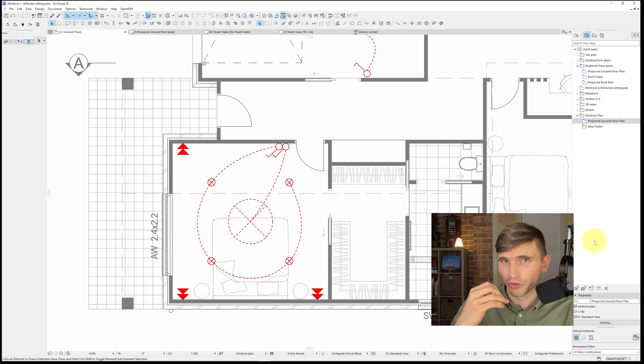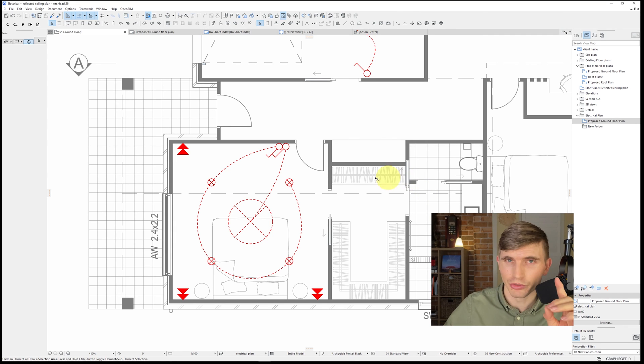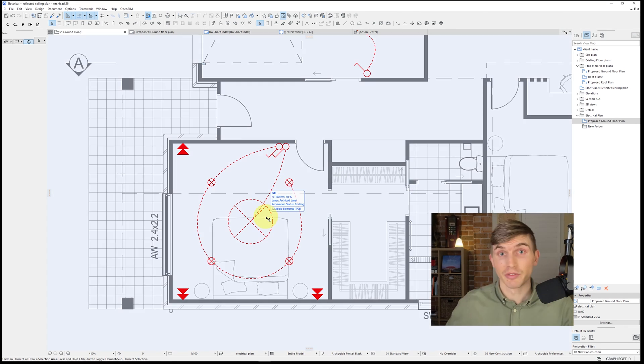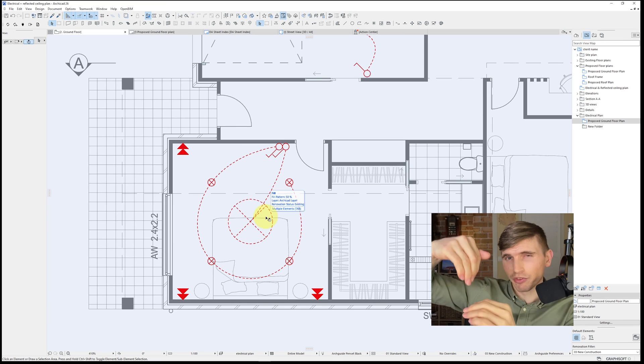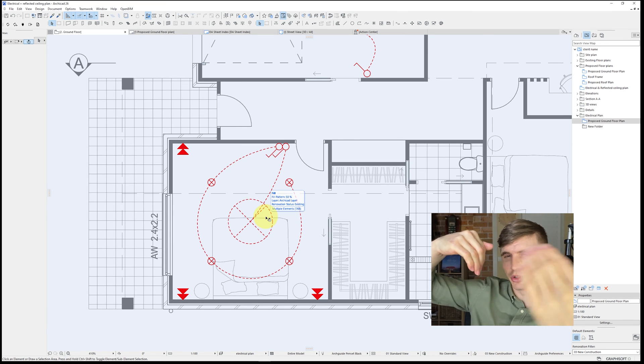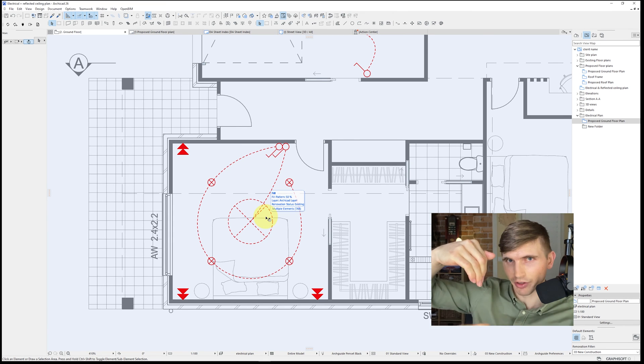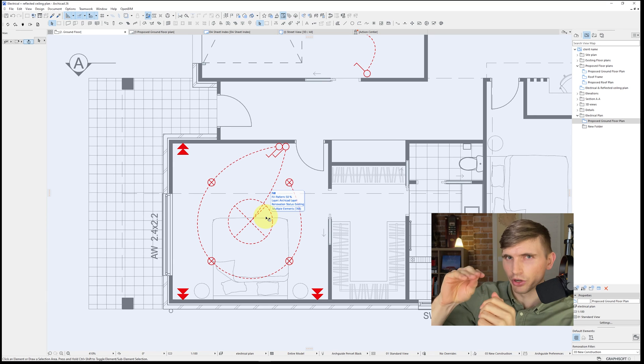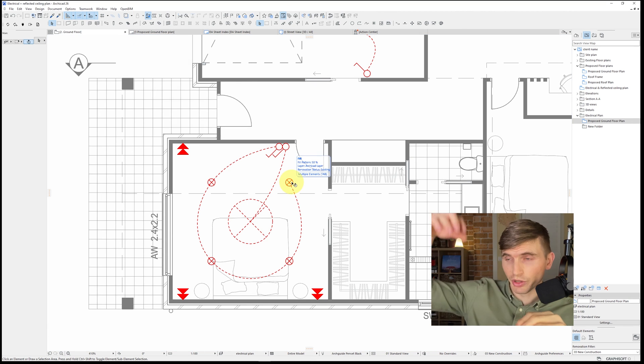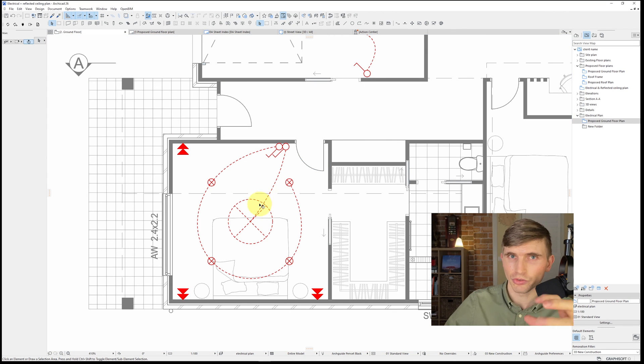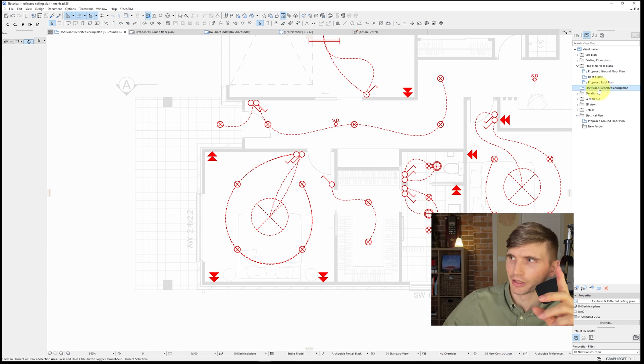One little trick I was taught when I was first learning how to do electrical plans was always to avoid having a light over the top of the fan. If you have it over the top of the fan, when the fan blades go past, it's going to create a strobing effect. Strobing, which is like a light turning on and off really quickly. So we try make sure that we've got lights adequately distance from fans in any of the different rooms.